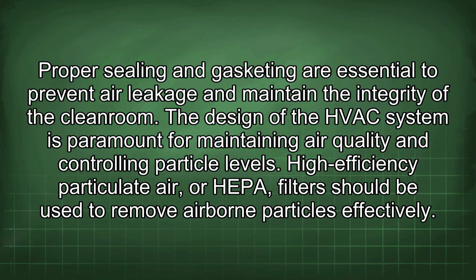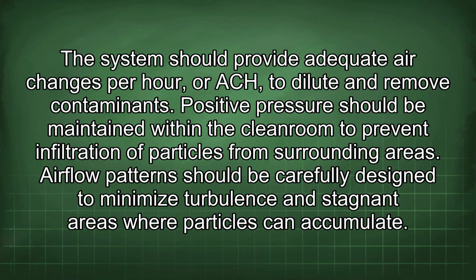The design of the HVAC system is paramount for maintaining air quality and controlling particle levels. High-efficiency particulate air, or HEPA, filters should be used to remove airborne particles effectively. The system should provide adequate air changes per hour, or ACH, to dilute and remove contaminants.